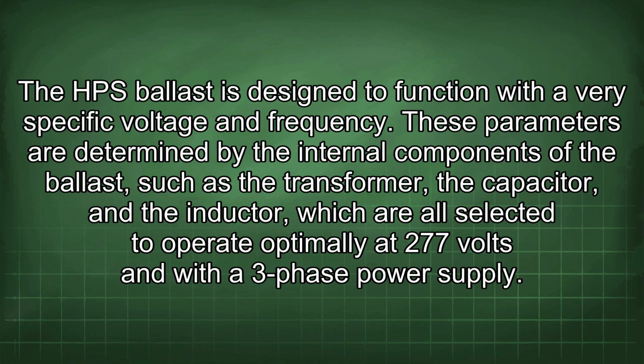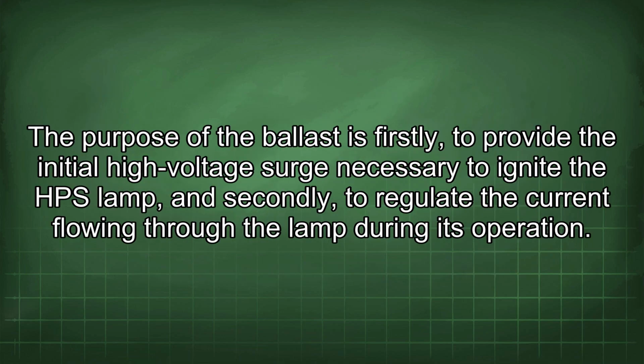The HPS ballast is designed to function with a very specific voltage and frequency. These parameters are determined by the internal components of the ballast, such as the transformer, the capacitor, and the inductor, which are all selected to operate optimally at 277 volts and with a 3-phase power supply. The purpose of the ballast is firstly to provide the initial high voltage surge necessary to ignite the HPS lamp, and secondly, to regulate the current flowing through the lamp during its operation.